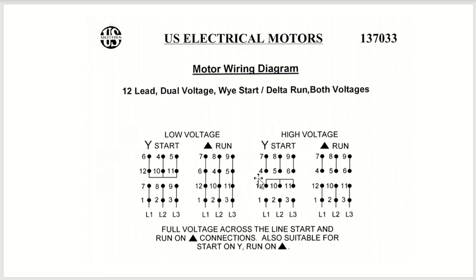For the high voltage, if you're doing Y delta with the 12-lead motor on high voltage, you would internally connect the 4 and 7, 8 and 5, 9 and 6 together. Those would stay that way, and your 6 leads that would be coming out would be your 1, 2, 3, and then this would actually be your 6, 4, 5, 12 is 6, 10 is 4, and 11 is 5. And then when you do the shorting of 4, 5, and 6 for the Y configuration, you power 1, 2, 3. When you put it into the run configuration, you power 1, 2, 3, and then 12, 10, 11.